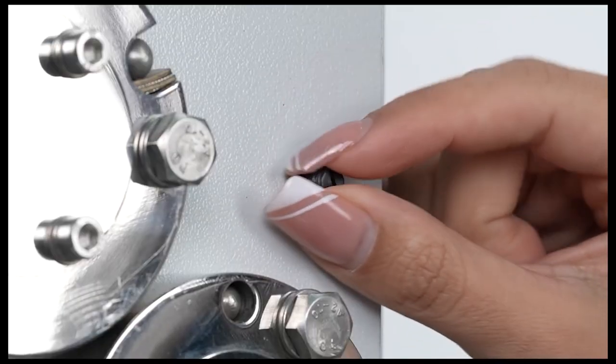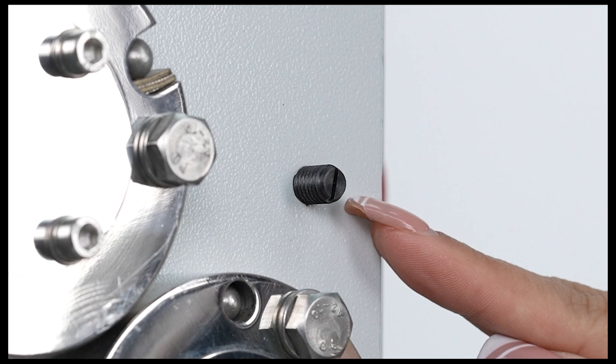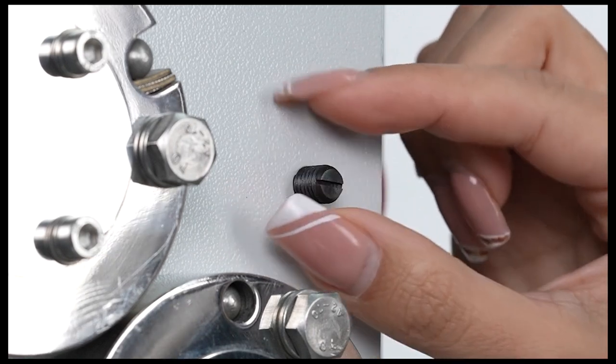During the compression of the roller balls, this screw is turned counterclockwise to remove the crushing unit, cleaning window unit. After cleaning the space between the roller balls with a brush, the unit is placed back in position, and the compression screw is turned clockwise to compress.